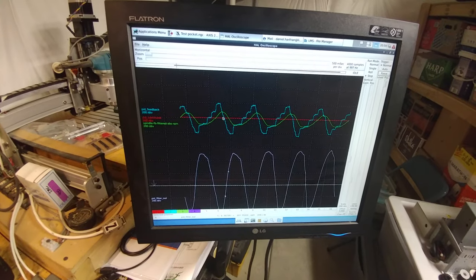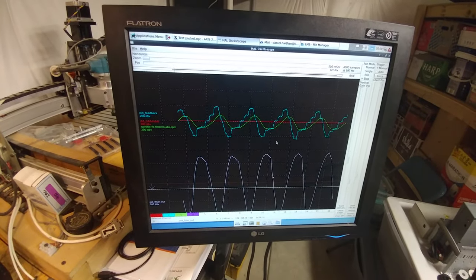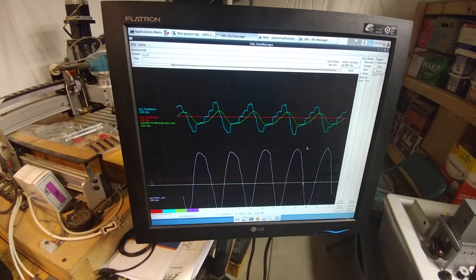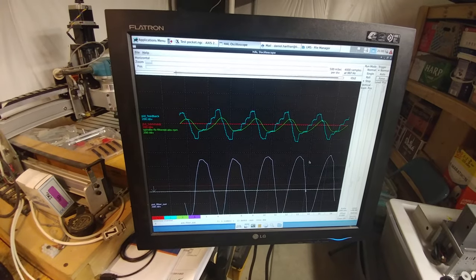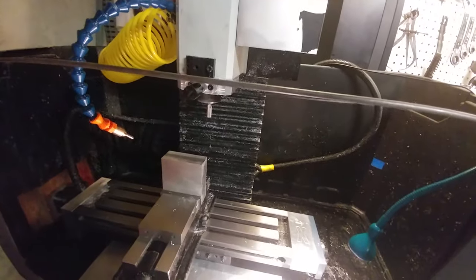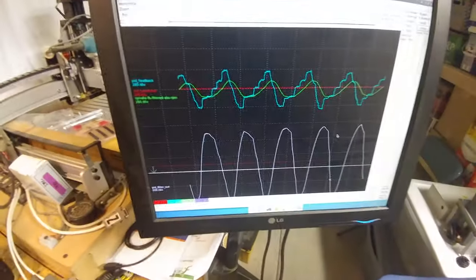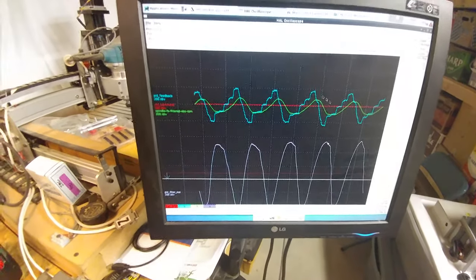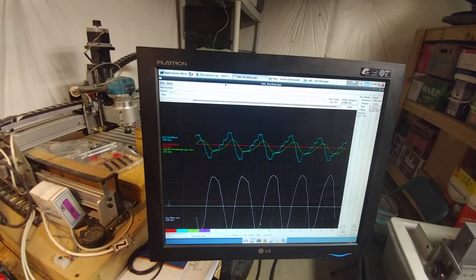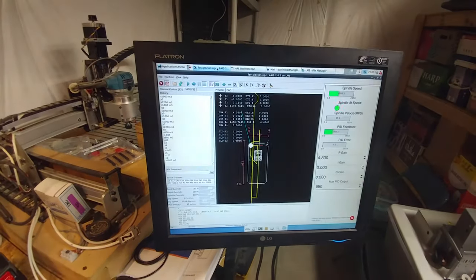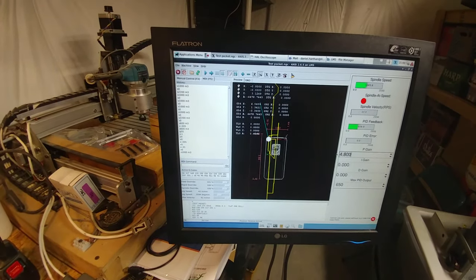I found that the wavelength is approximately 0.645 seconds, so it's oscillating about every 0.6 seconds for one full wavelength for its RPM. Using that, I used the predetermined formulas for the Ziegler-Nichols method, and they were pretty useful in tuning the machine.